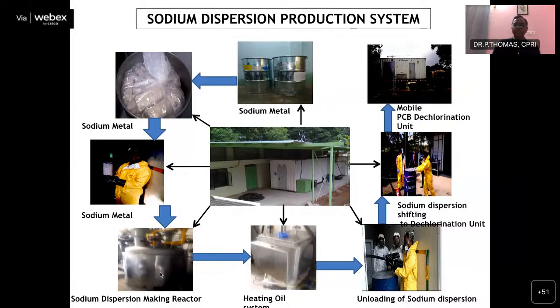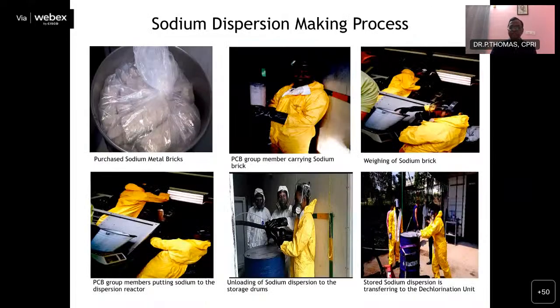This dispersion is used for treating the PCB oil. When you treat the oil, the PCB reacts with the sodium, forming sodium chloride among other things. If the particle size of the sodium dispersion is more than 30, 40, or 50 microns, the reaction is slow. Whereas if it's less than 10 microns, the moment you add the sodium dispersion to the PCB oil, the reaction takes place in 2 hours.